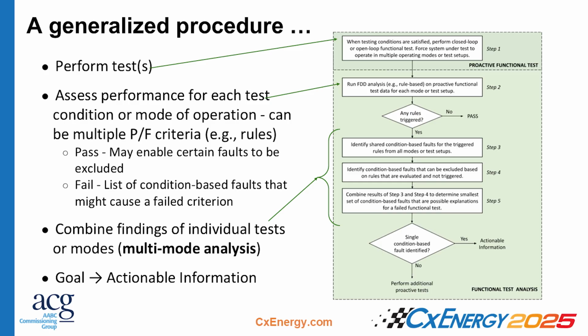So the first step here is to have pre-test conditions being met. If you're testing airflow control in a VAV, you want to make sure the supply fan is on, right, before you do any of that. If you're testing reheat valve operation, you want to make sure the boiler and the heating hot water pumps are on before you do that. So make sure everything's set up for your test to start. You then run through a series of functional tests, each with its own pass and fail criteria. And in some of the tests, we have follow-on testing if a certain functional test didn't pass, right? So we have some partners that just give you a fail-pass sort of a display once the functional tests are done.